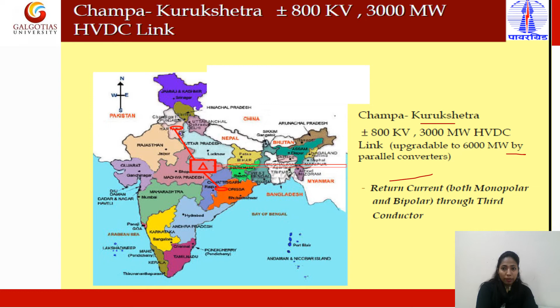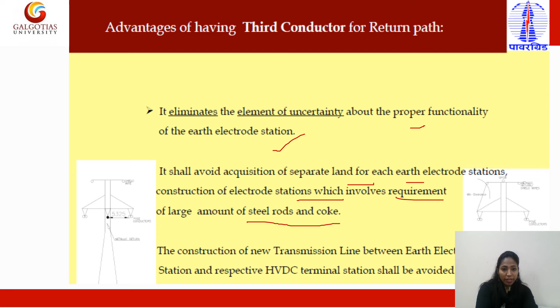Now, the advantages of having a third conductor for the return path: it eliminates uncertainty about the proper functionality of the earth electrode station, avoids acquisition of separate land for electrode stations, avoids construction of electrode stations which require large amounts of steel rods and coke, and avoids construction of new transmission lines between the earth electrode station and respective HVDC terminal stations.